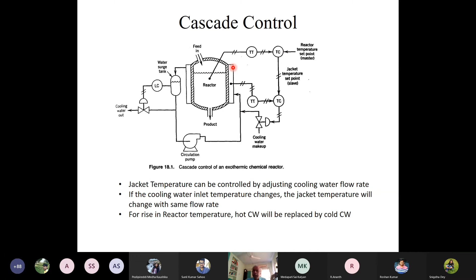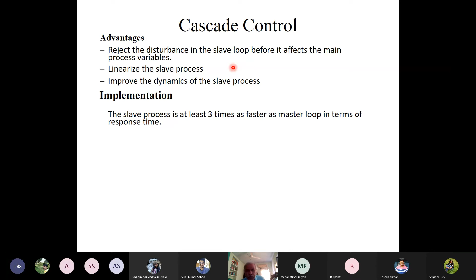Okay, so this is a very important thing when we are deciding to implement the cascade control strategy. We should first find out the speed of the slave process with respect to the master process. Secondly, the slave loop may not need to be controlled exactly at the set point. So tight control of the slave loop is not required. In fact, in many cases, you will find only a proportional controller is used in the slave loop. If I use only a proportional controller, then the speed of response of the control loop will be pretty fast, with an offset in the slave control loop, but that offset will not hamper the master control loop.